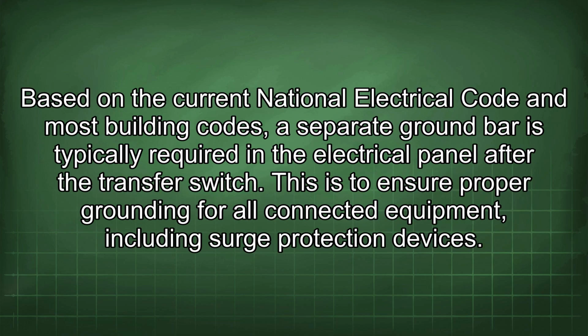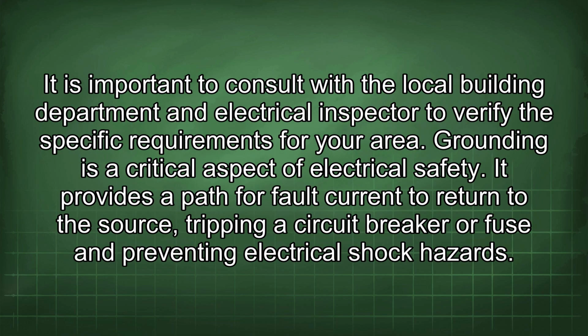Based on the current National Electrical Code and most building codes, a separate ground bar is typically required in the electrical panel after the transfer switch. This is to ensure proper grounding for all connected equipment, including surge protection devices. It is important to consult with the local building department and electrical inspector to verify the specific requirements for your area. Grounding is a critical aspect of electrical safety.